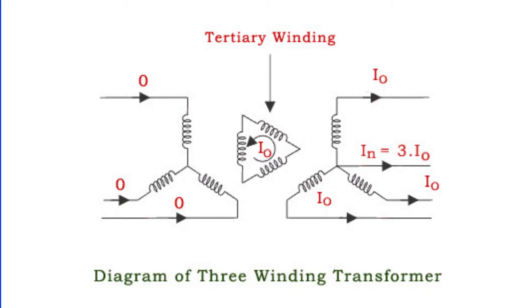The primary function of the tertiary winding is to reduce unbalance in the primary due to unbalance in three-phase load, redistribute the flow of fault current, and supply an auxiliary load at a different voltage level in addition to its main secondary load. This winding is connected in delta formation in a three-winding transformer, which aids in limiting the fault current in the event of a short circuit from line to neutral.